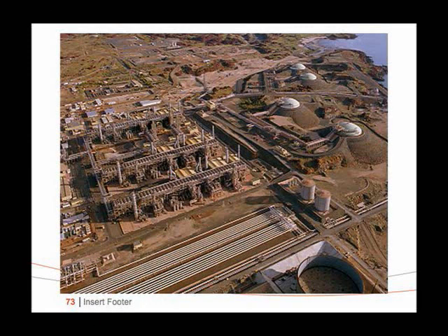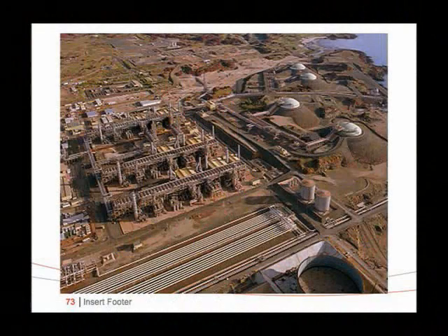But it's also in industry. We did some work with Amory Lovins. This is an LNG plant. These are the heat rejection, which are fin fan coolers. Amory says this is the size of a battleship, if you want to get an idea of scale. It's very tall, it's elevated, but when the wind blows in summer, northern hemisphere summer, when the price of LNG is highest, the output of the plant is the lowest. Because the hot air blows in, and the outlet of this gets into the inlet of this, and the outlet of this goes into the inlet of this, and the production of LNG drops like crazy. You basically have to take methane and cool it to minus 173 or something. So heat rejection is a common problem, and common stuff like nowhere for the heat to go, nobody looks at that.